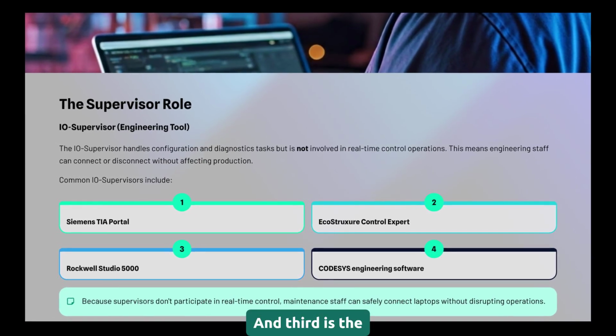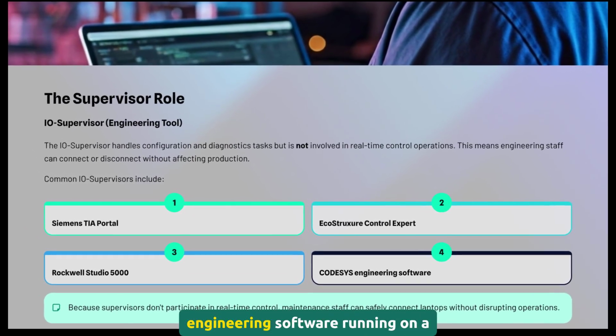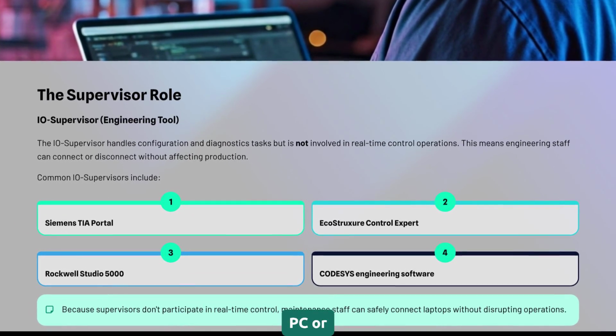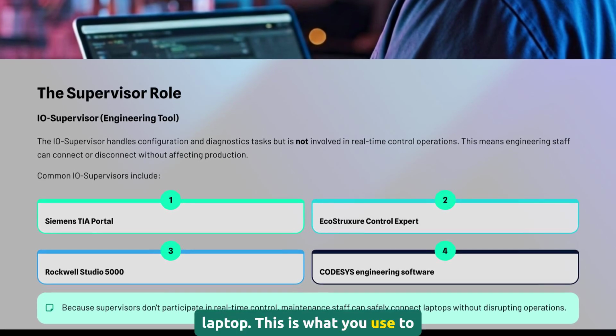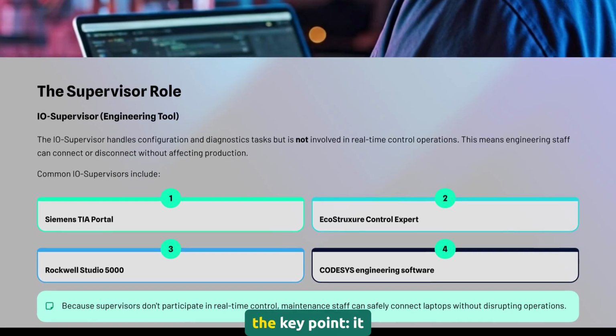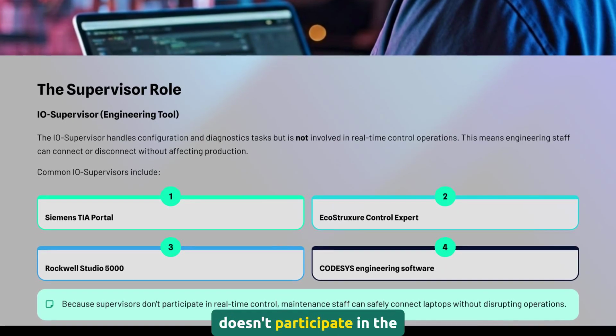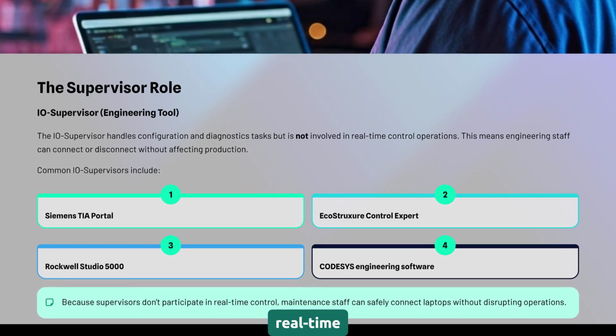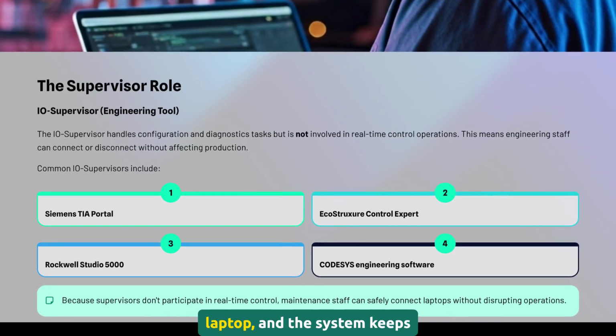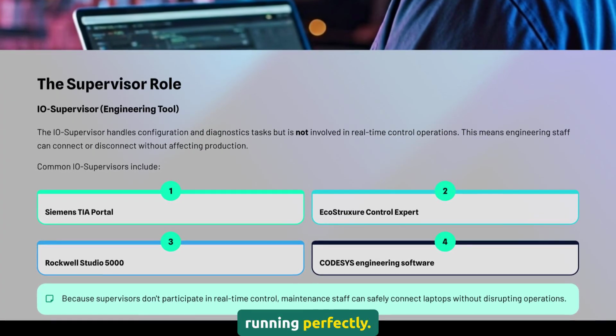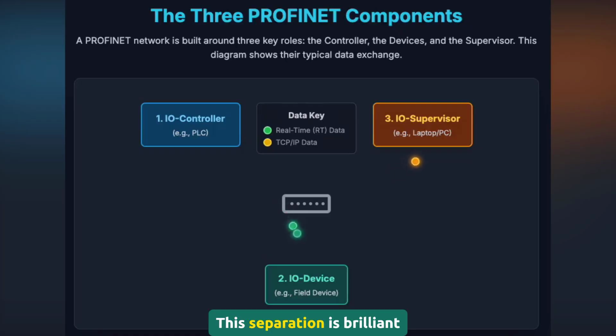And third is the I/O Supervisor. That's your engineering software running on a PC or laptop. This is what you use to configure everything, but here's the key point. It doesn't participate in the real-time control. You can unplug your laptop and the system keeps running perfectly. This separation is brilliant because it means you can do diagnostics and troubleshooting without affecting production. I can't tell you how many times this has saved me when tracking down issues on a live line.